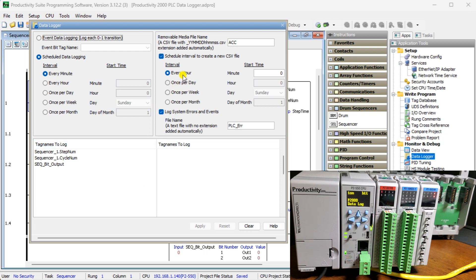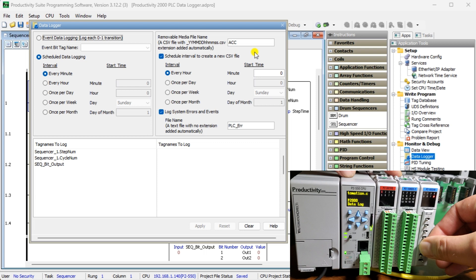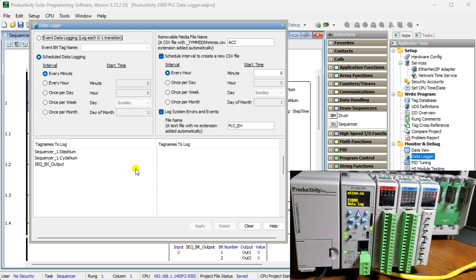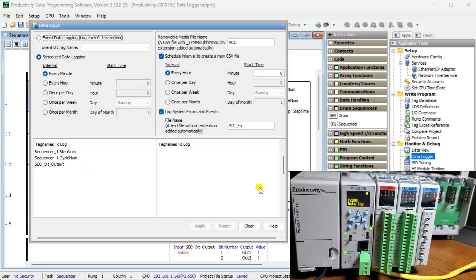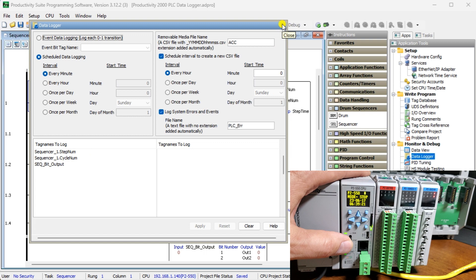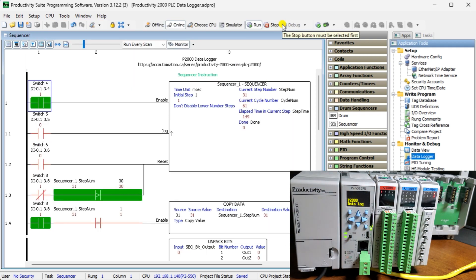Our example will log values every minute, so it's scheduled logging. The file media name will be ACC — the underscore year, month, day, hour, minute, second, dot CSV will be added to the file name. Every hour we will start a new CSV file. Log system errors and events to a file called PLC Error. Our tag names will be from our sequencer example discussed previously. Hit Apply, then use the upper X in the corner to close the data logger window.